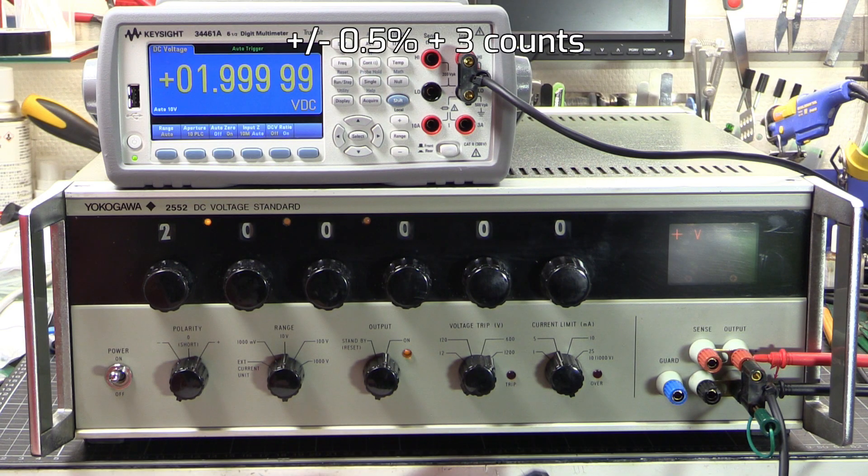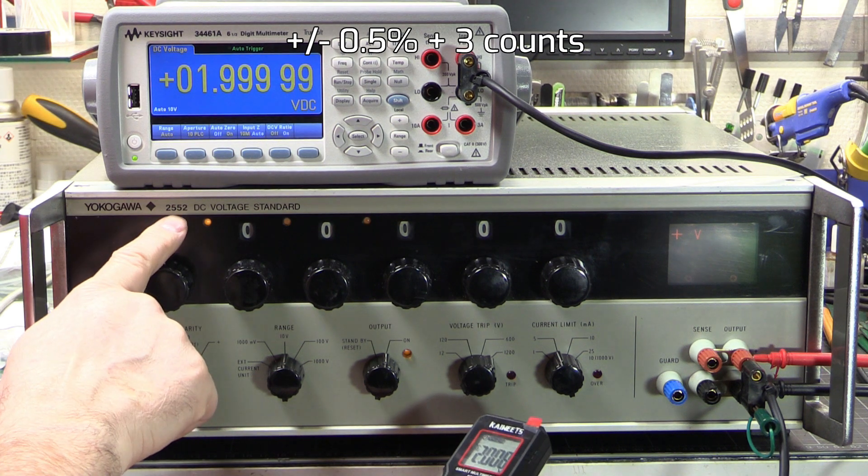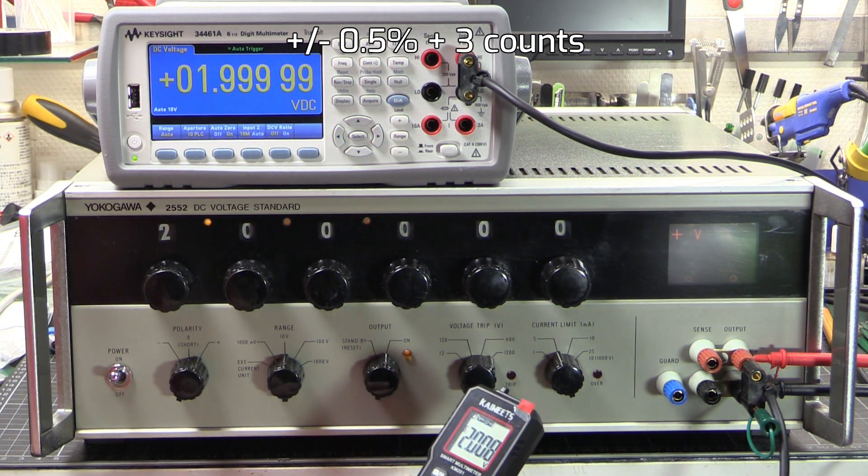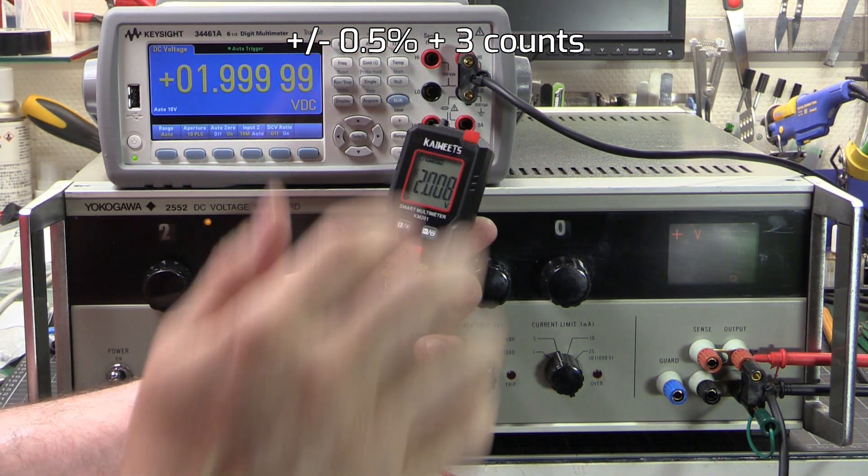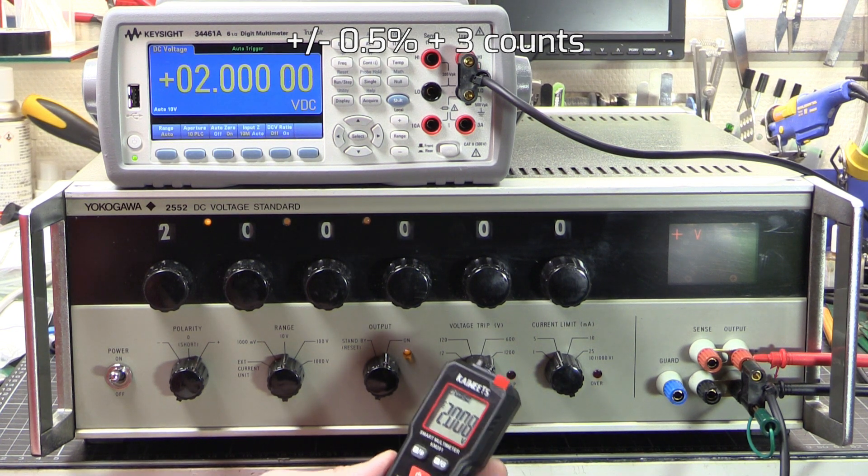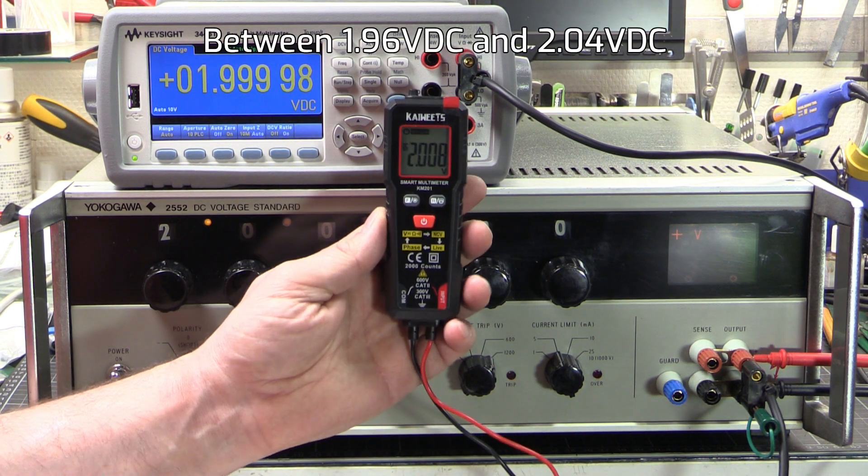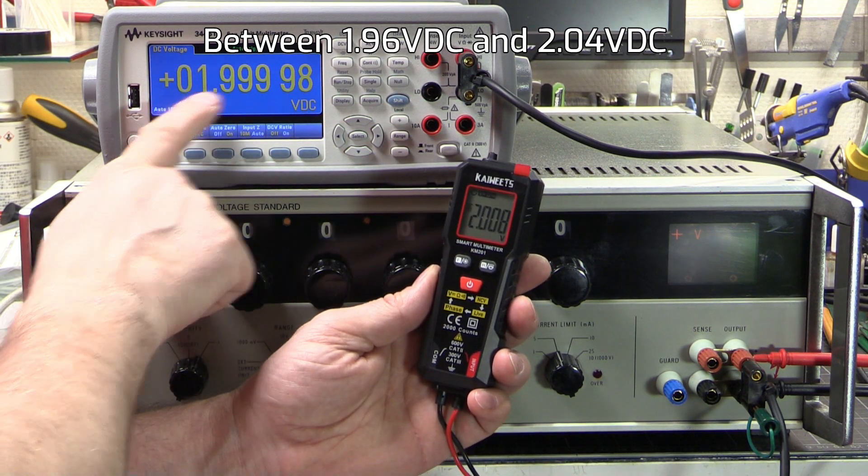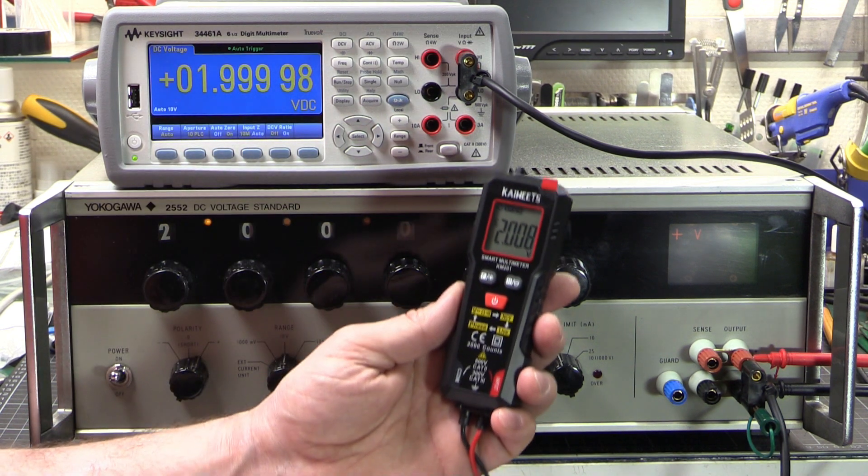And the DC voltage test now. We've got the Yokogawa 2552 DC voltage standard. And we've got it set to 2 volts. We're going to do the same deal. Looking on here compared to here. And it should be below 2.04, between 1.96 and 2.04. And we've got 2.008 for basically exactly 2 volts output. That one's good.